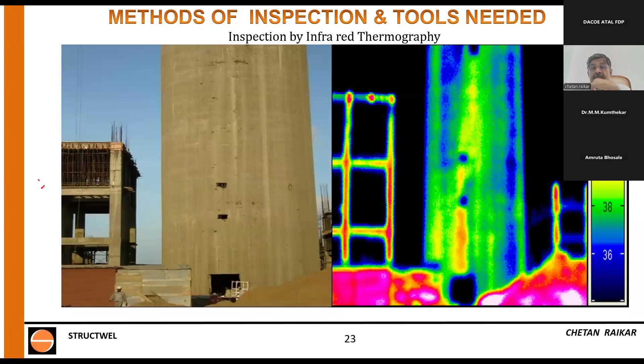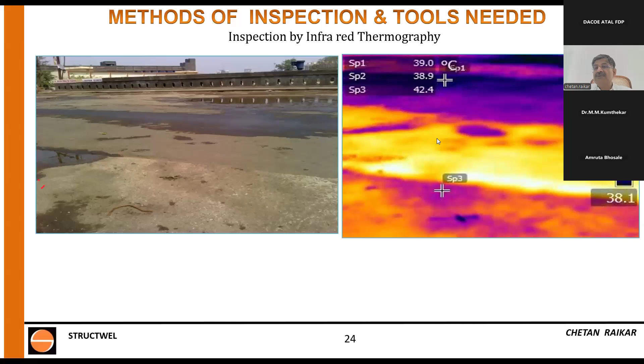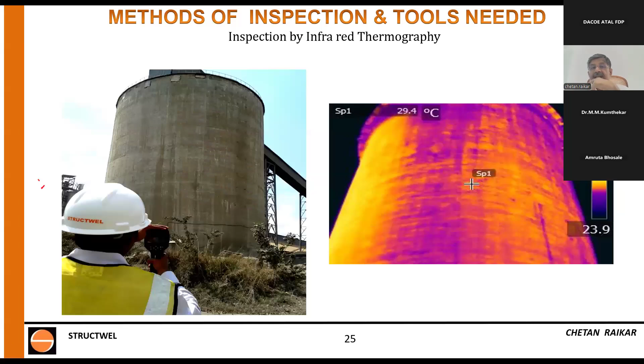This is how you can inspect the top surface of a terrace also, using an IR camera to find debonding. You wash the whole terrace, allow it to settle for 10 minutes, let it dry out and take IR camera photos. You will know the hollows because the water will go inside, and the temperature difference will show you different areas, as you see on the right hand side. This is how the photographs of the top portion of a terrace can be seen with an IR camera.